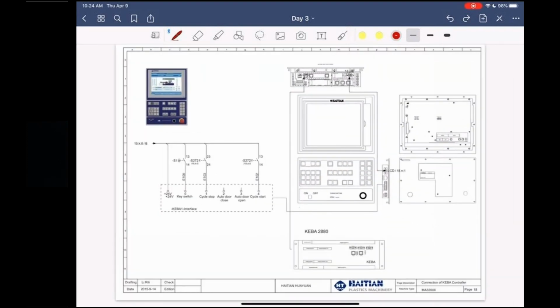The only difference to this is the 4030 machines. If anybody has an older 4030 machine, the actual CPU is located behind the screen itself. So all the connections are done inside the screen, and there's only one wire going from the CPU to the cabinet. It's not even a CPU inside the cabinet, they're just a bunch of IOs. So you have one connector going to the IOs inside the cabinet.